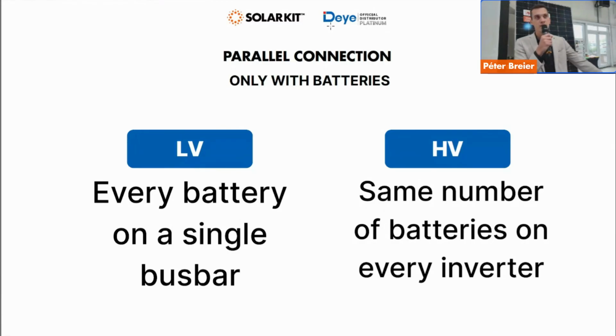If you have low voltage series, you just install the batteries, you put them on one power rail, and from that power rail, you connect to all of the batteries. So you will have one cluster of batteries connecting to all of the inverters. In the high voltage series, however, you will need the exact same amount and the same type of batteries on each inverter. If you don't do that connection, the inverters will not work in parallel mode.